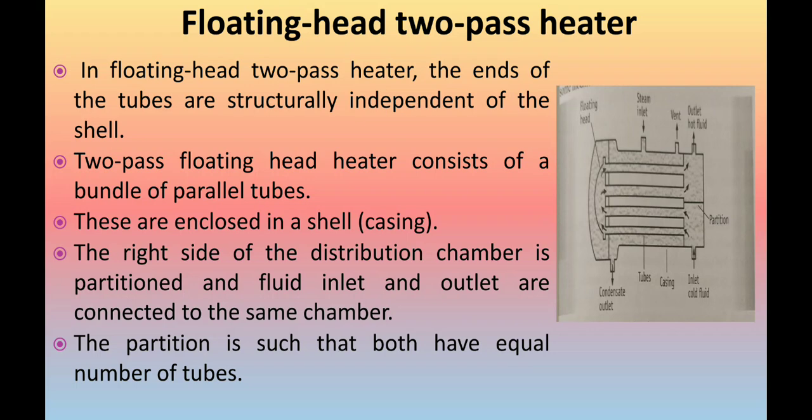If we talk about the construction of two-pass heater, it consists of the same components as a tubular heater with some modifications. The two-pass floating head heater consists of a bundle of parallel tubes. These are enclosed in a casing. The right side of the distribution chamber is partitioned, and the fluid inlet and outlet are connected to the same chamber.